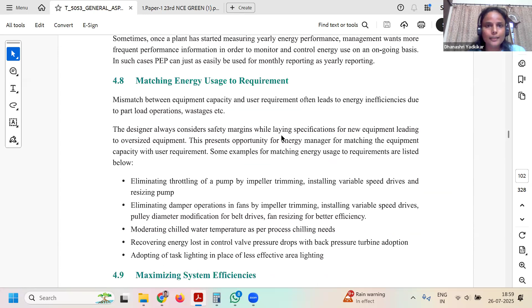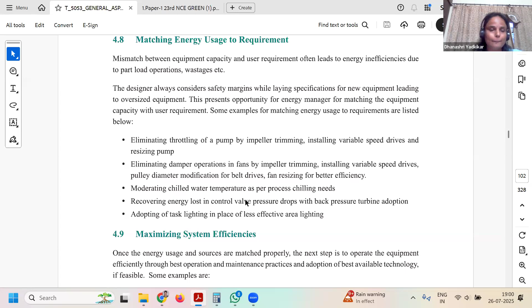Then matching energy use to the requirement. A mismatch between the equipment capacity and user requirement often leads to energy inefficiencies. The designer always considers safety margins while laying specifications for new equipment, leading to oversized equipment. This presents an opportunity for the energy manager to match the equipment capacity with the user's requirement. Some examples are eliminating the throttling of the pump by impeller trimming, installing variable speed drives (VFDs), resizing the pump depending on the heads, eliminating damper operations, moderating chilled water temperature, recovering energy lost in the control valves, and adopting task lighting in place of less effective area lighting.